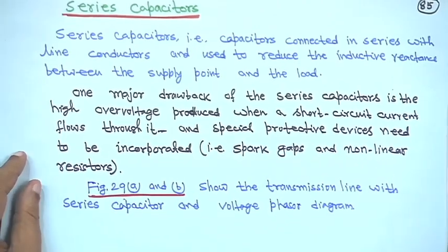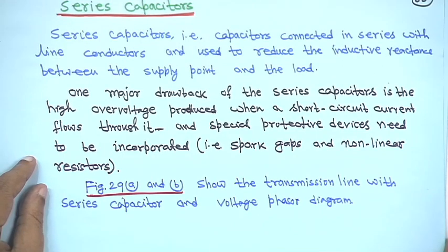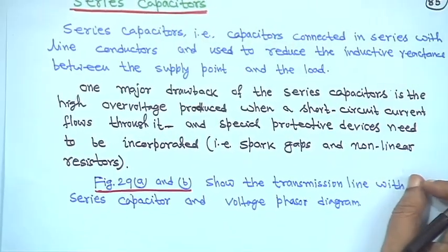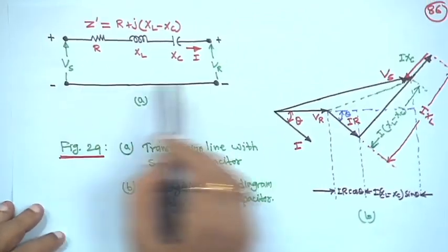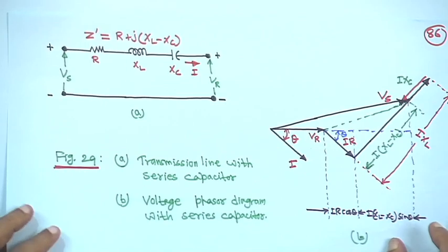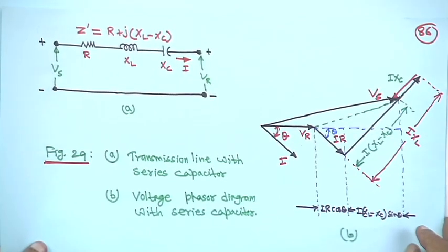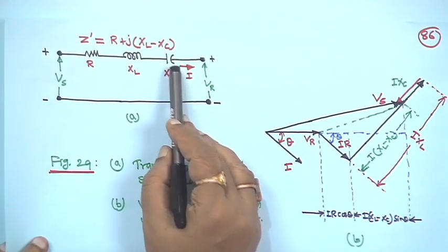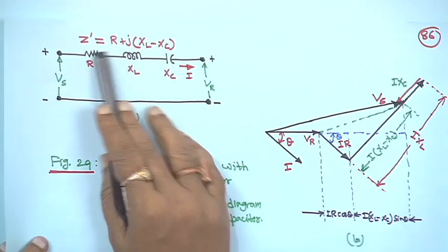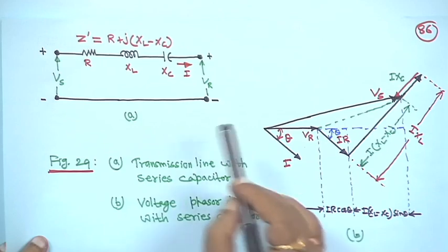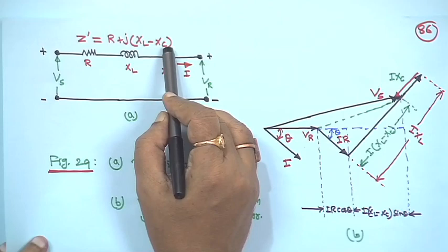When connecting a series capacitor in a line, a lot of protection is needed and one must be very careful. In the series capacitor circuit, with sending end voltage V_S and receiving end voltage V_R, the line has resistance R and reactance X_L, and the series capacitor is in series. The impedance becomes Z_dash = R + j(X_L − X_C). Because of X_C, the X_L − X_C component reduces, naturally reducing the voltage drop and improving the receiving end voltage.